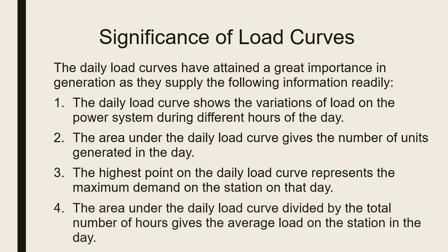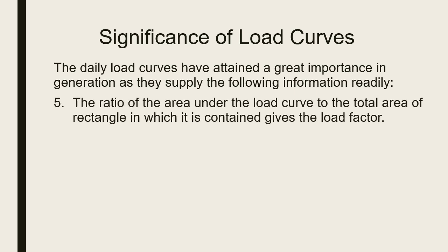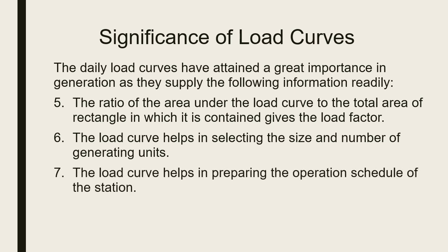Fourth, the area under the daily load curve divided by the total number of hours gives the average load on the station in the day. Fifth, the ratio of the area under the load curve to the total area of the rectangle in which it is contained gives the load factor. Sixth, the load curve helps in selecting the size and number of generating units. And last, the load curve helps in the preparation of the operation schedule of the station.